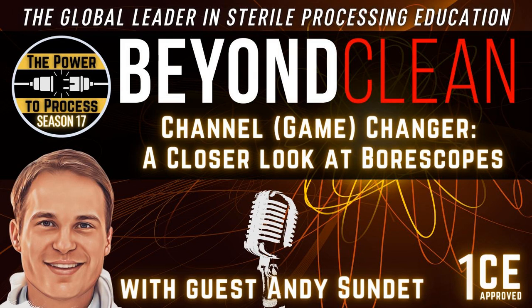And that kind of damage, let's hope that we're catching it before it's bigger damage, right? So the second thing being damage, discoloration would be a third one. I would try to match these all with the letter D to help make it simpler. So debris, damage, discoloration. Discoloration could be staining. We had a lot of questions about rust or stuff that looks like rust. So discoloration is just something that's not the same color or shade as the rest of the lumen, and you can point that out pretty easily with the borescope.